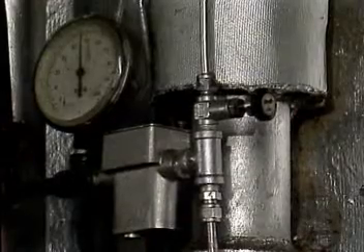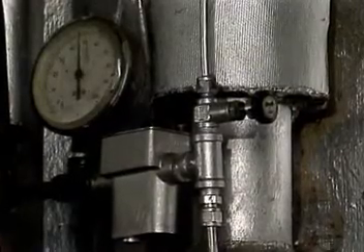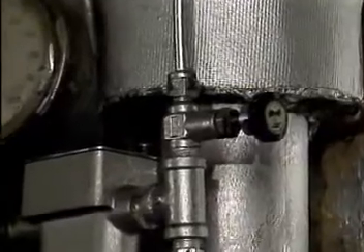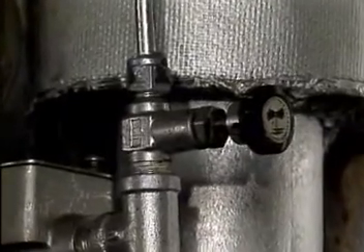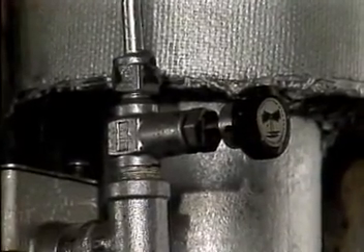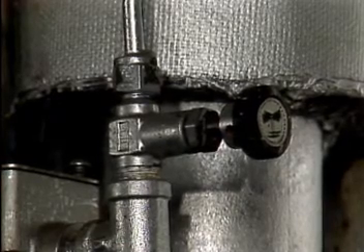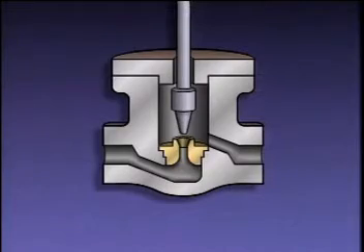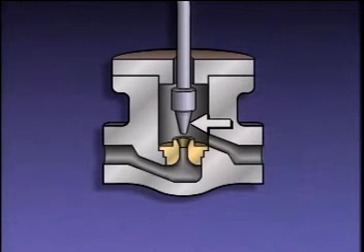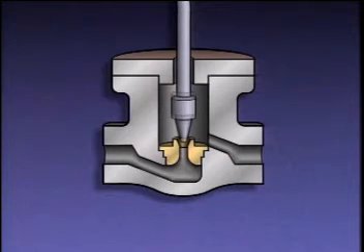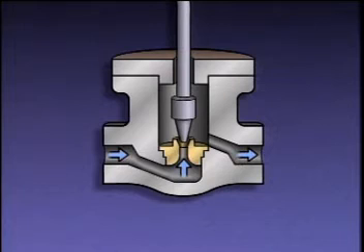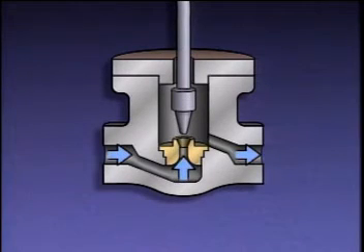This is another type of globe valve called a needle valve. Needle valves are usually smaller than other globe valves and are designed to give fine control of flow in small diameter piping. A needle valve has basically the same parts as other globe valves, but its disc is shaped differently, like a needle. The needle extends deep into the seating area of the valve.